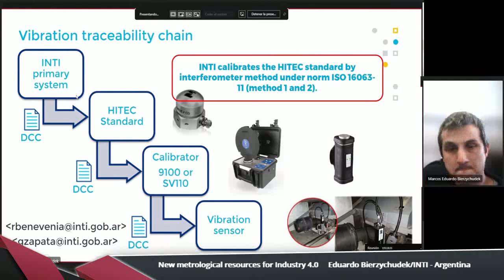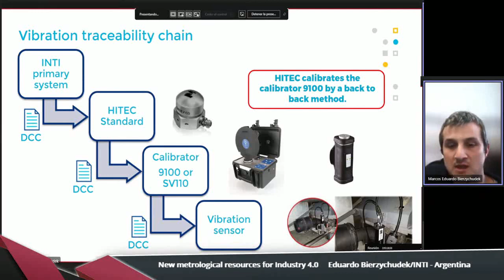In the frame of this project, one of the objectives is to update this system to a model system 1. INTI already implemented the digital calibration certificate for these accelerometers and calibrators. HITEC calibrated the 9100 calibrator by a back-to-back method. We select this instrument because it has a DC output where we can measure directly the internal accelerometer signal. And HITEC has a 6.5 digit multimeter for this task.